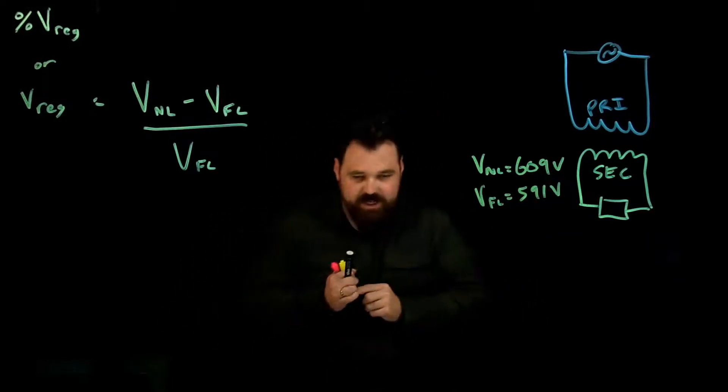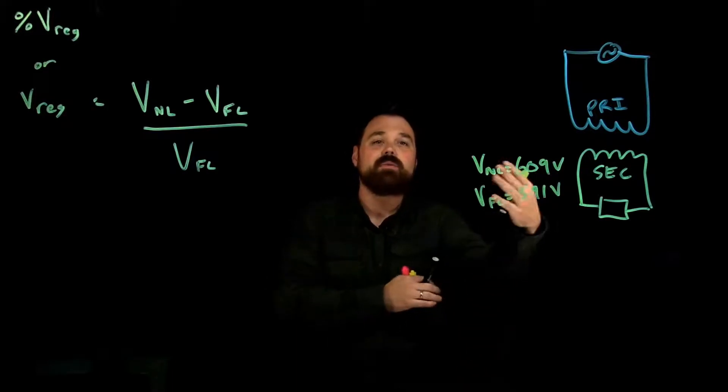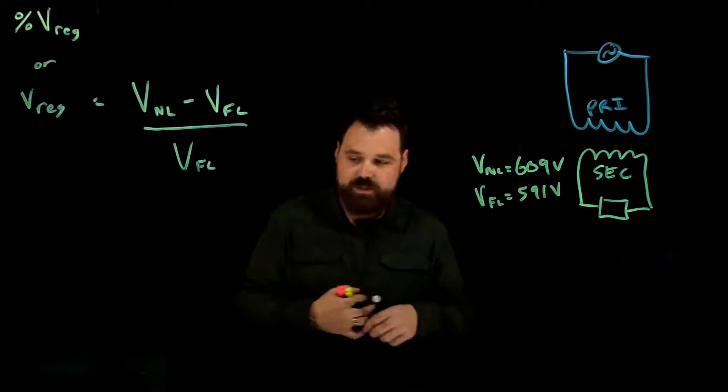So when we energize the transformer, initially measure the voltage without a load, we read 609. Once we add a full load, we get 591 volts.